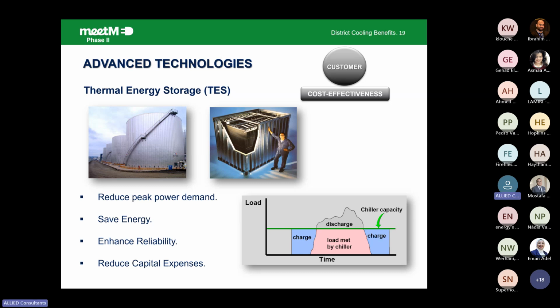Cost and the reduction in cost. If you are taking the first plant that we built, the cost of a chiller plant was around 30,000 Egyptian pound per ton. But if you are taking a thermal storage and we are taking the storage out of the chillers, then we are getting around 7,000 Egyptian pound per ton. So we have reduced the cost of the plant by having the thermal storage, because thermal storage is just a tank, and the cost of constructing the tank is much less than having a plant with the same capacity that we are withdrawing from the thermal storage.